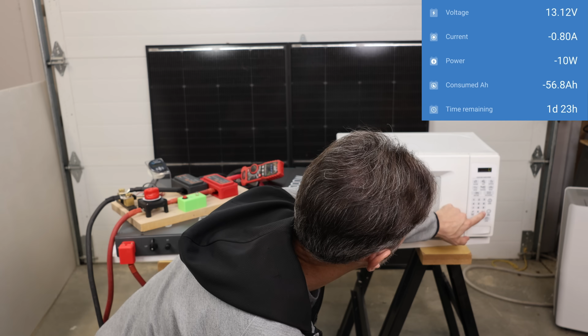The inrush actually wasn't as high as I thought, it was only 47 amps. The running current's higher than that at about 105, but still less than the coffee pot. Microwave runs fine, no issues. Battery doesn't even care, we're nowhere near its limit.